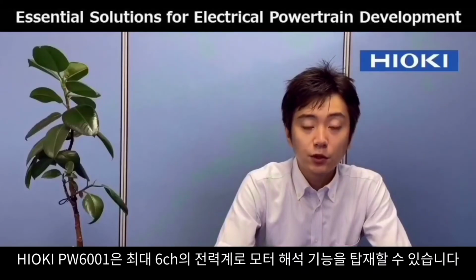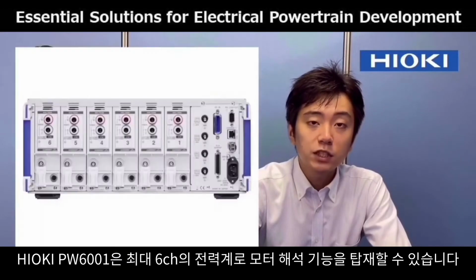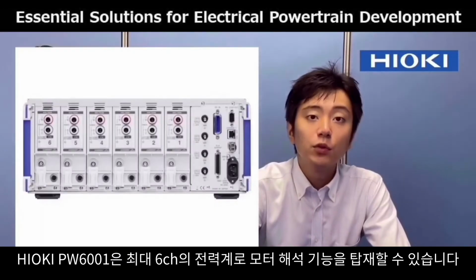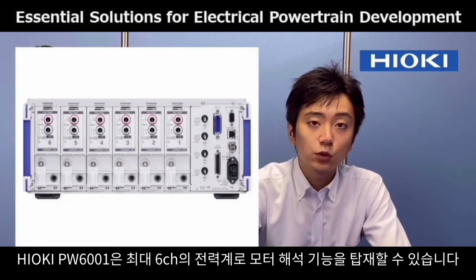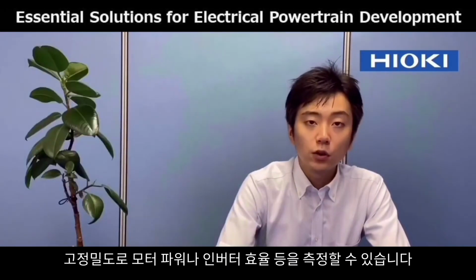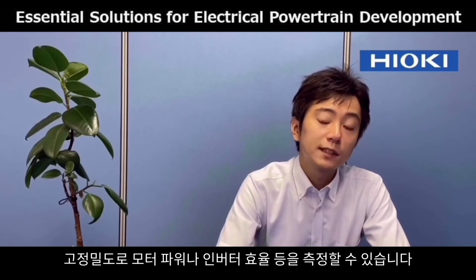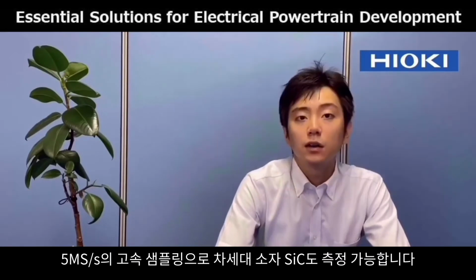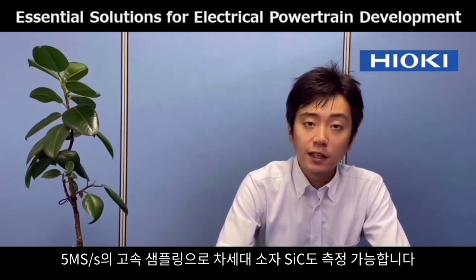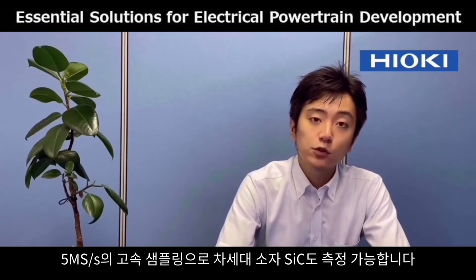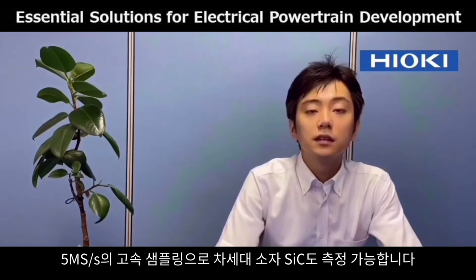Hioki's PW6001 is a power analyzer with up to 6 channels. It can also be equipped with a motor analysis function. The user can measure motor power and inverter efficiency with very high accuracy. High-speed sampling of 5 megasamples per second enables measurement of even next-generation SiC semiconductors.